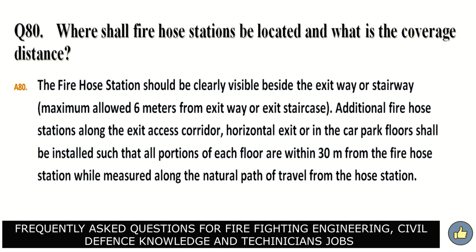Where shall fire hose stations be located and what is the coverage distance? The fire hose station should be clearly visible beside the exit way or stairway, maximum 6 meters from exit way or exit staircase. Additional fire hose stations along the exit access corridor, horizontal exit or in the car park floor shall be installed such that all portions of each floor are within 30 meters from the fire hose station while measured along the natural path of travel from the hose station.